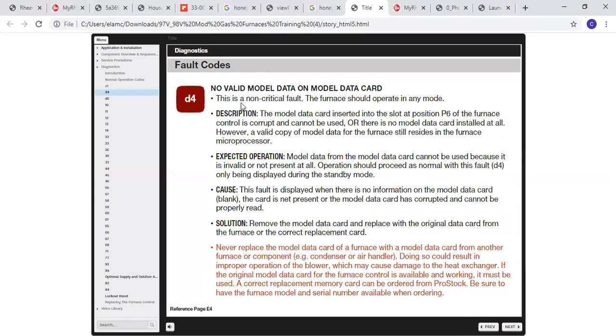We have another one here. A D4 is no valid model data on your card. This is a non-critical fault. It will still operate in most modes. Expected operation, since model from the data card cannot be used, it will still proceed as normal, but you'll get the D4 fault. The solution is to remove the model data card and replace with the original or the correct replacement.